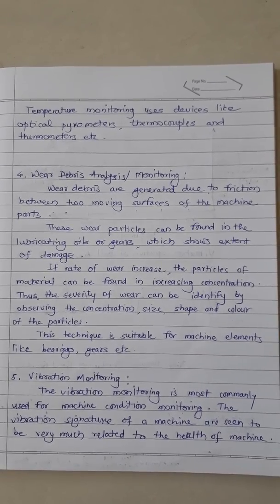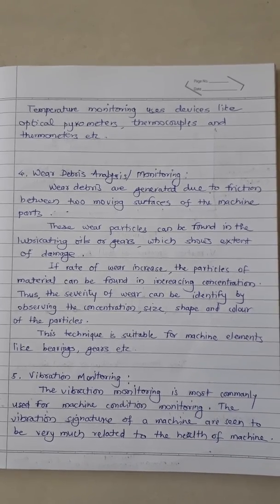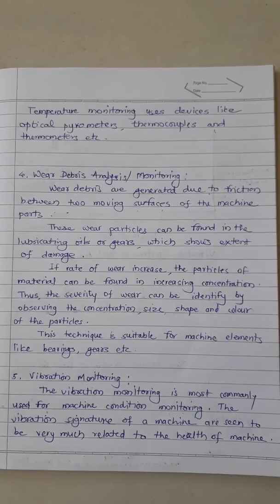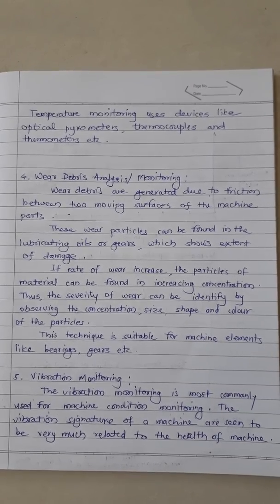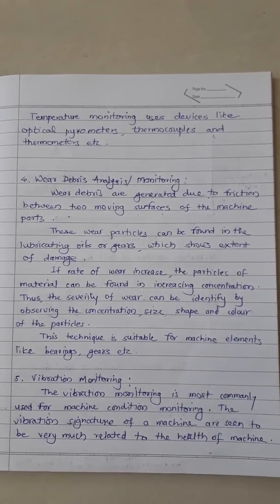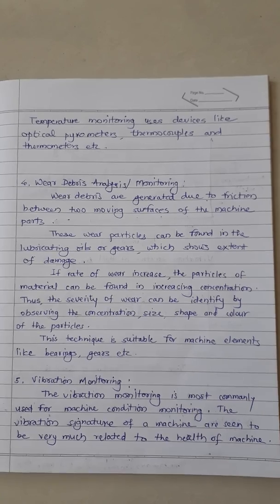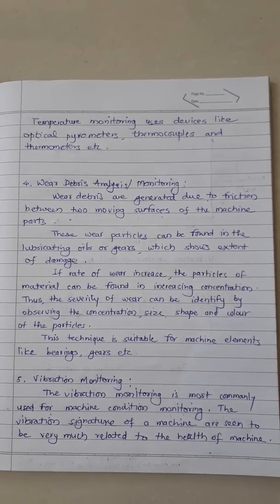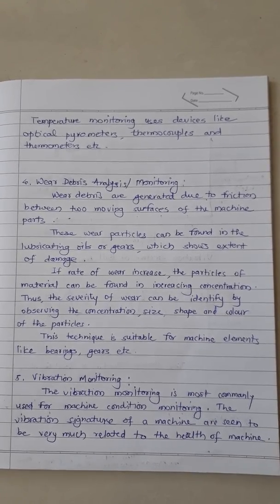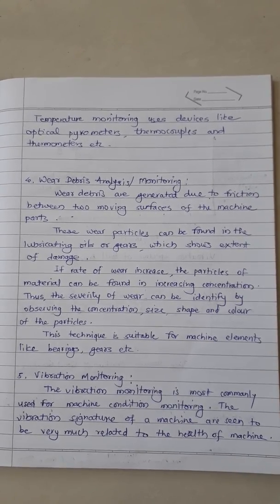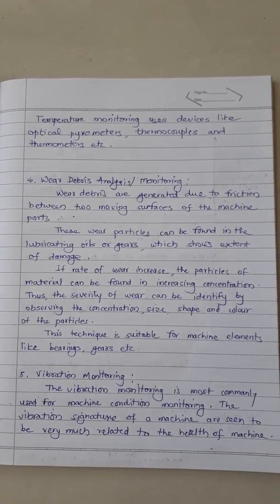Wear debris analysis or monitoring: wear particles are generated due to friction between two moving surfaces of machine parts. These wear particles can be found in the lubricating oils or greases, which shows the extent of damage. If the rate of wear increases, the particles of material can be found in increasing concentration. Thus the severity of wear can be identified by observing the concentration, size, shape, and color of the particles.